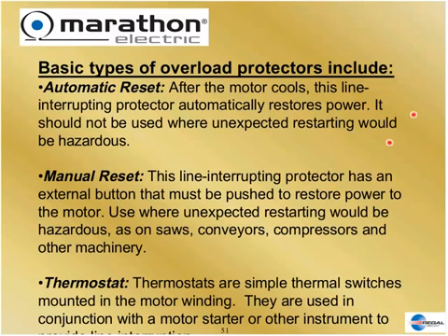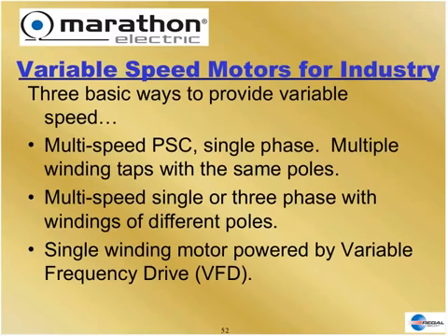The third type is a thermostat switch, used primarily in three-phase motors but sometimes single-phase. It's not a line-interrupting device — it's simply a thermal switch that clicks open inside, and its leads connect to the controller signaling it's getting hot. The controller trips the motor starter or control panel to take the motor off the line.